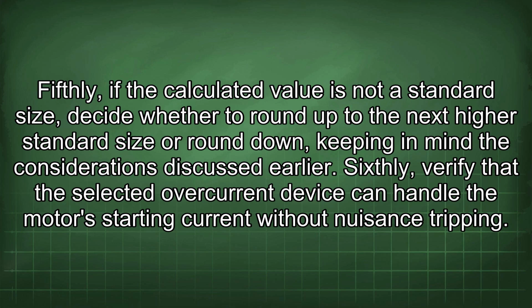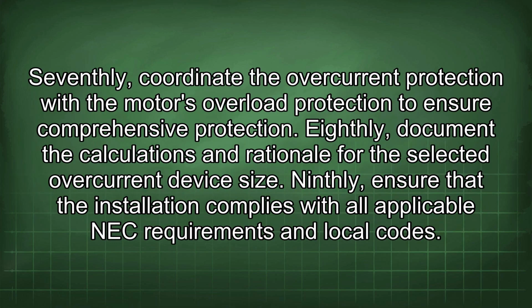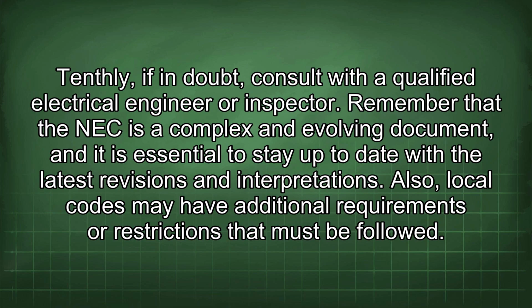Sixthly, verify that the selected overcurrent device can handle the motor's starting current without nuisance tripping. Seventhly, coordinate the overcurrent protection with the motor's overload protection to ensure comprehensive protection. Eighthly, document the calculations and rationale for the selected overcurrent device size. Ninthly, ensure that the installation complies with all applicable NEC requirements and local codes. Tenthly, if in doubt, consult with a qualified electrical engineer or inspector.